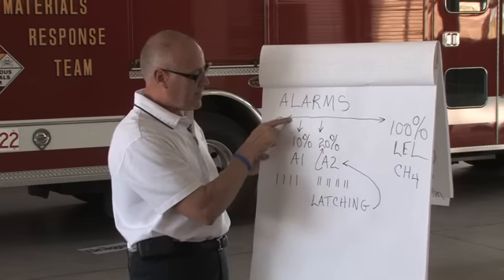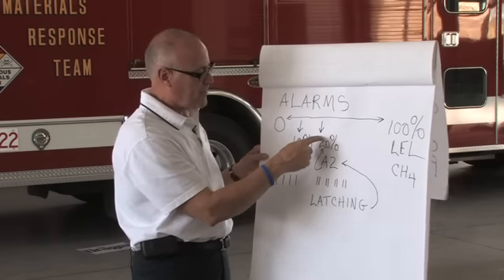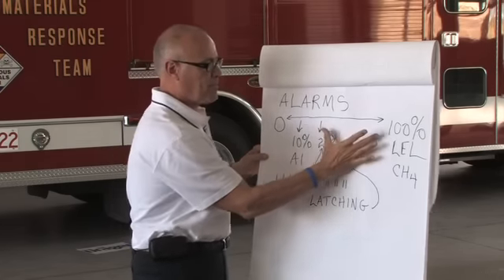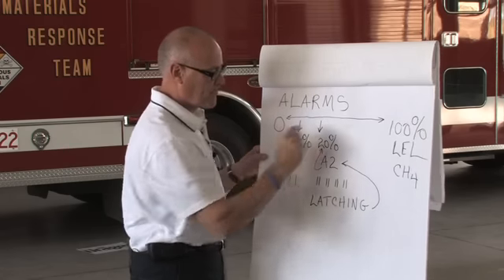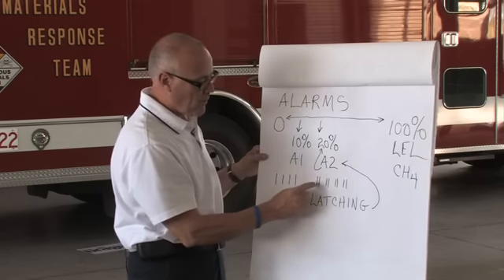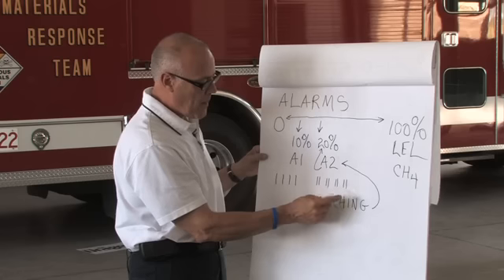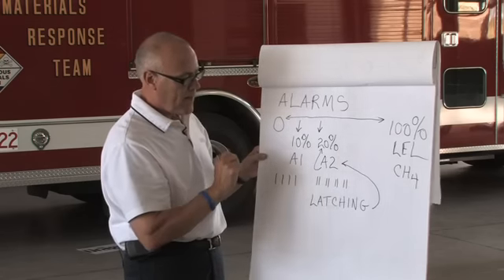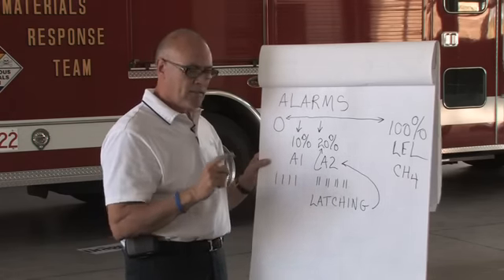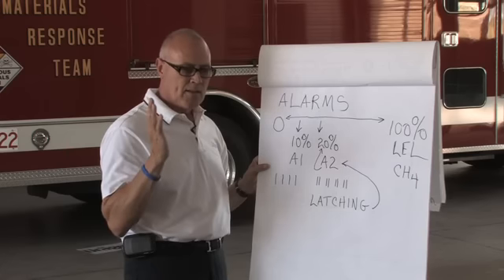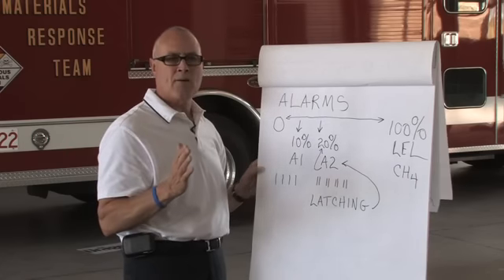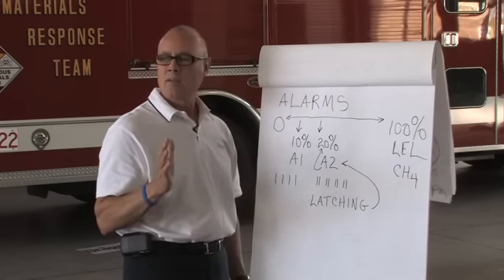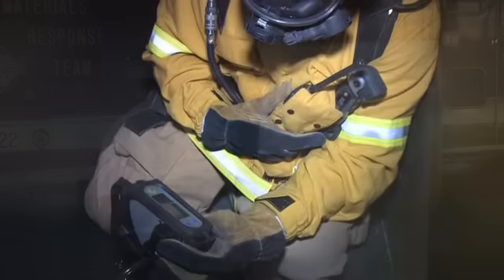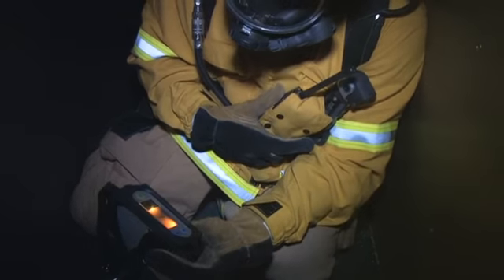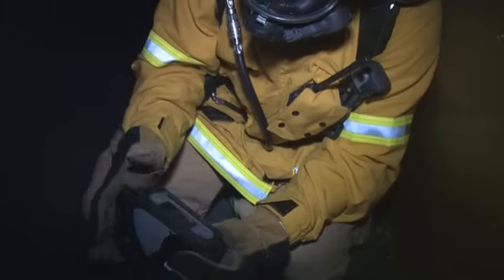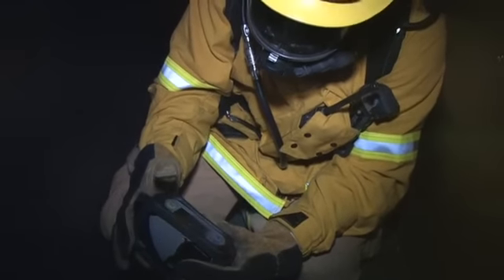Okay? As the gas increases, you'll hit 20% of the LEL. Again, 80% safety factor to this point. Now you will get a double tone. Okay? And in addition, you'll notice that double tone. If I heard a gas detector right now, and I heard that tone, I would know that I've got a severe problem. An A1 alarm, A2 alarm.